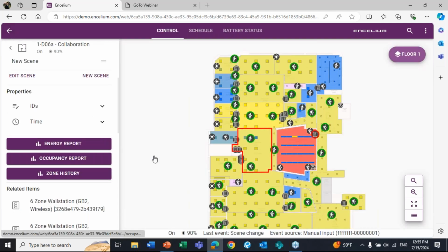This is one of the tools that facility people now have that say, okay, I can see if a device is offline. If somebody calls me up and says, hey, I have an issue, I can actually look at this and say, well, okay, don't go chasing the sensor and save time because it's probably not the sensor. Look at something else that might be the core issue of what's going on.